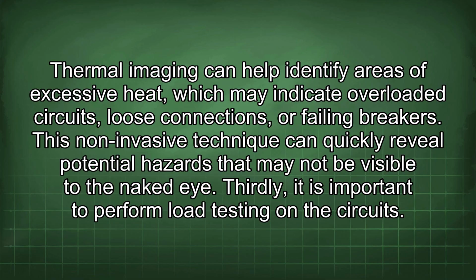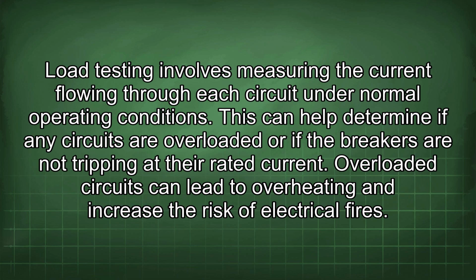Thirdly, it is important to perform load testing on the circuits. Load testing involves measuring the current flowing through each circuit under normal operating conditions. This can help determine if any circuits are overloaded or if the breakers are not tripping at their rated current. Overloaded circuits can lead to overheating and increase the risk of electrical fires.